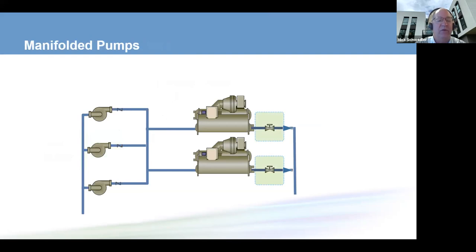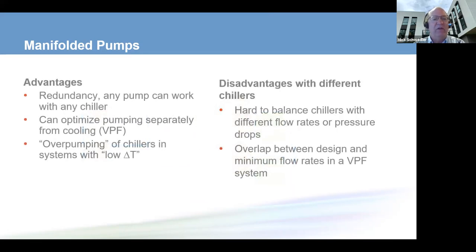And now let's go to manifolded pumps. Well, the first thing we see with manifolded pumps is since they pump into a header, we now will have to make sure that we have isolation valves because we don't want water flowing through an inactive chiller and diluting or increasing the supply chilled water temperature that's going out to our system. Benefits of this is now any pump can work with any chiller. So our redundancy is much higher.